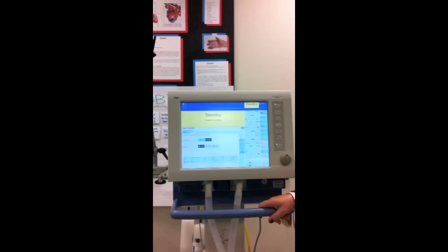So no questions? On the plateau on this one, it's automatically calculated for you, right? You don't have to push... No, you have to do an inspiratory hold. You can never get a plateau without doing an inspiratory hold. So you always have to do that. It's under special procedures, and there's also a button right on the screen for it. Does it calculate compliance or resistance? Most of the time, but it's finicky like the other ones. For the midterm, you can write down the compliance, but don't be surprised if I ask you what the calculation is, because you still need to know how to calculate it. Ventilators don't always give us the numbers we want, so sometimes we have to calculate them manually.